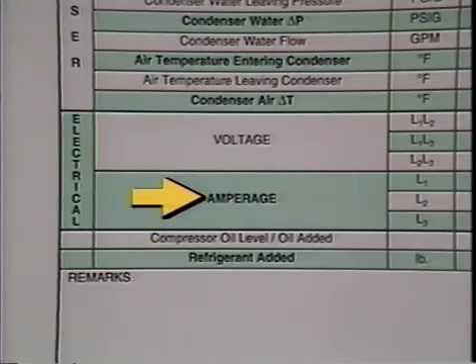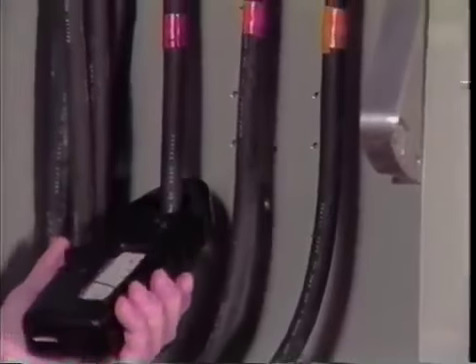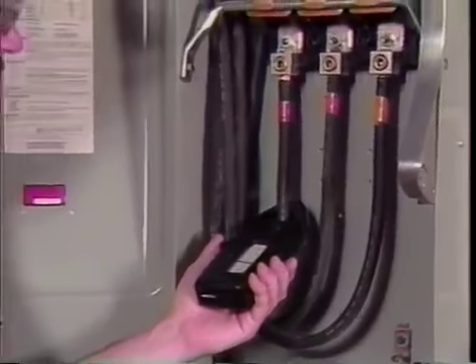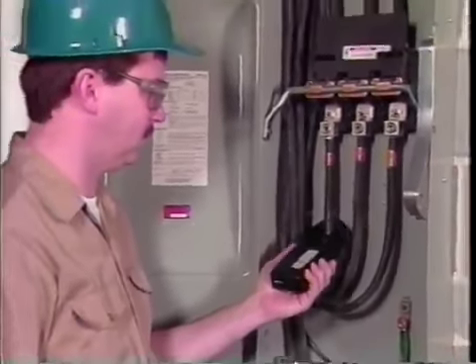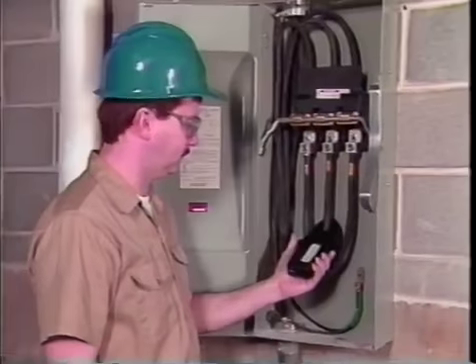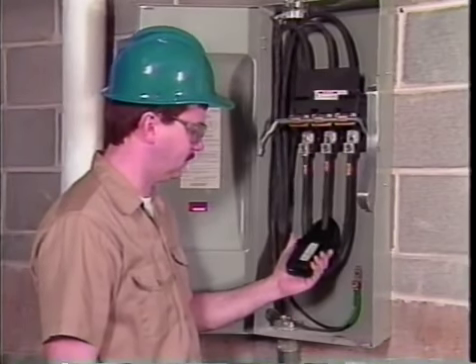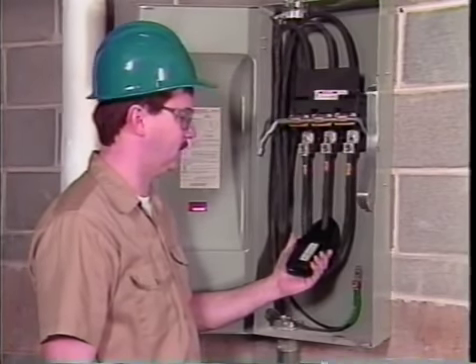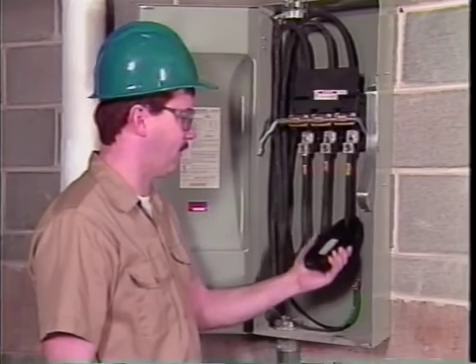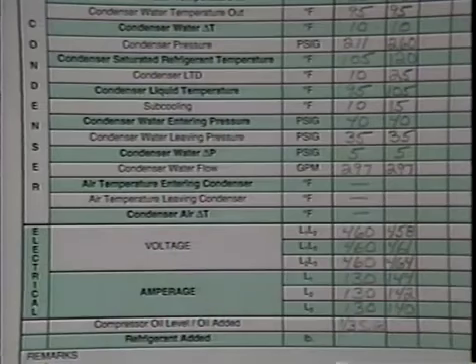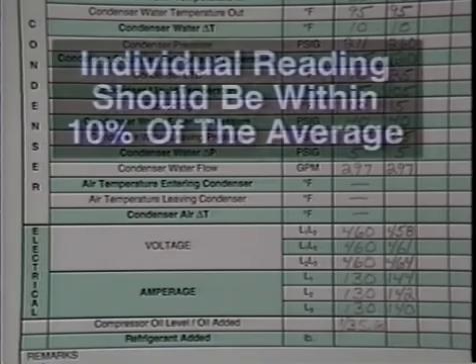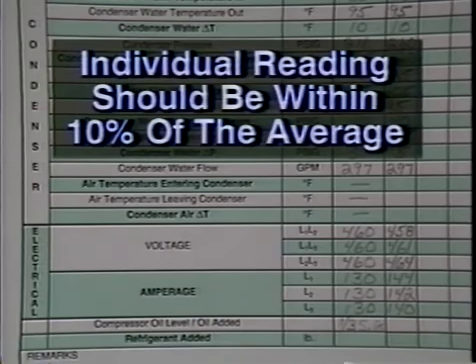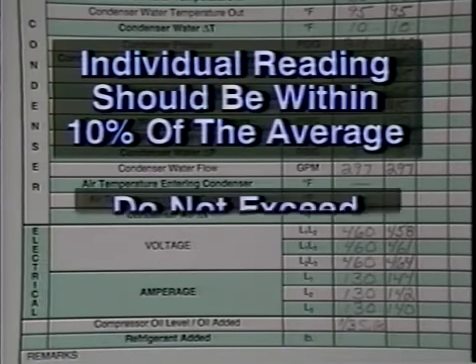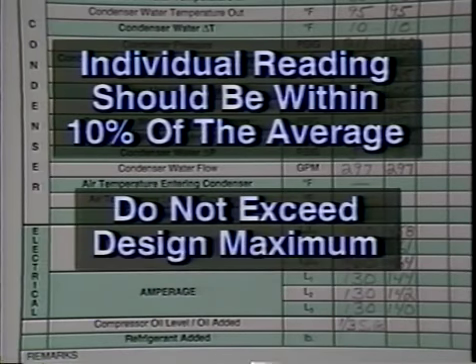Motor amperage. Using a clamp-on ammeter, record the chiller's total motor amperage. But make sure the unit has stabilized first. It should operate at least 30 minutes before taking ampere readings. Check each power lead of the chiller. Then, total and average the readings. The individual amperage readings should be within 10% of the average amperage. Also, the average amperage should not exceed the design maximum.